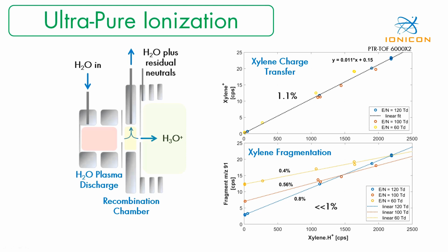A potential fragment on mass over charge 91 is, dependent on E/N, always below 1%. But please see that as an upper boundary, as I have extracted the data from a calibration gas experiment with around a dozen compounds in the sample. So a fraction of this low mass over charge 91 signal can actually be caused by an impurity of an interfering ion.